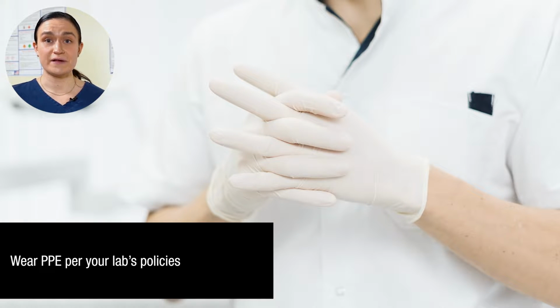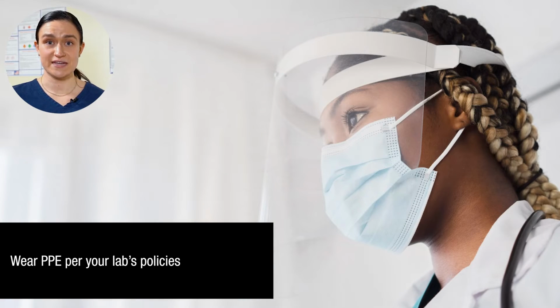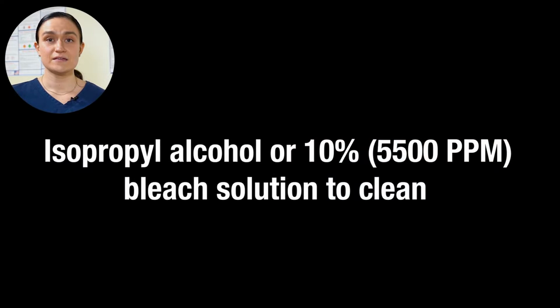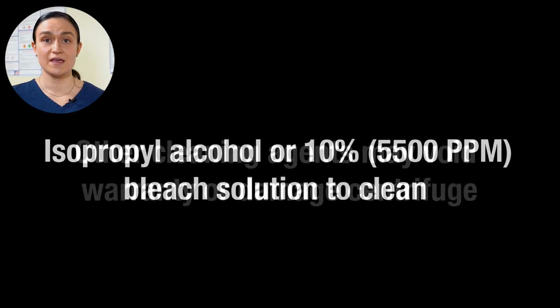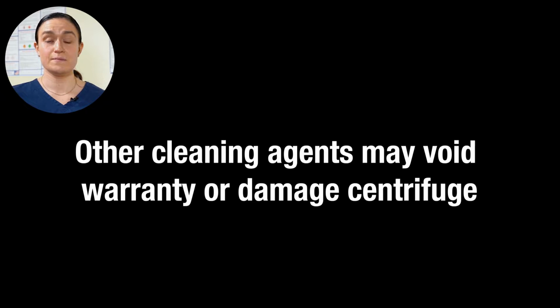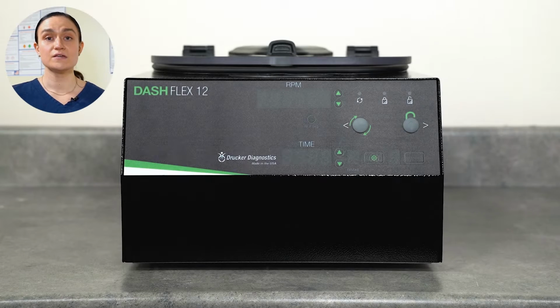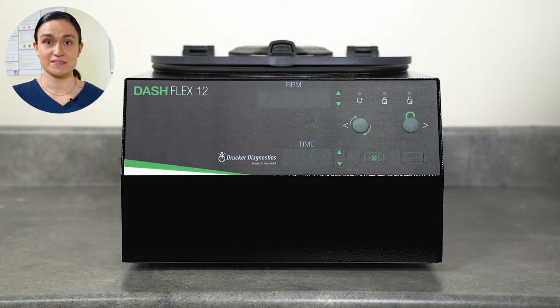Next, make sure that you're wearing any appropriate personal protective equipment as determined by your lab. When cleaning the Flex 12, you should only use isopropyl alcohol or 10% 5500 ppm bleach solution. Use of any other material may void the warranty and damage the centrifuge. Do not submerge the centrifuge at any point during the cleaning process.